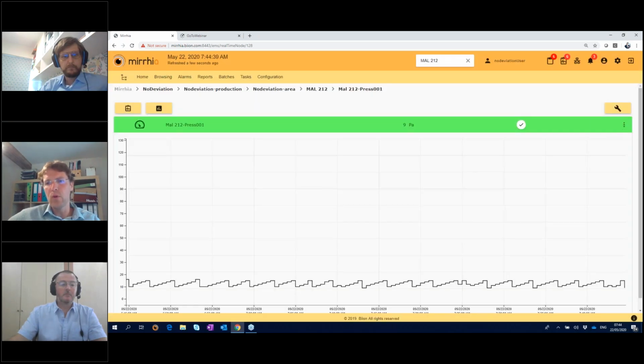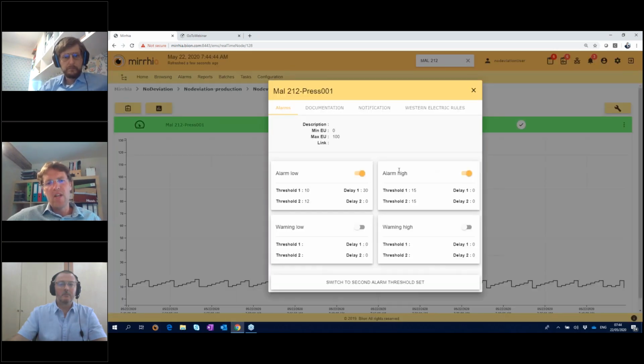Also, if I look at the properties of these sensors, you see that we manage alarm and warning, and we manage 2 sets of thresholds. Of course we manage delay too. This can be useful for pressure sensors, to make sure we don't get an alarm every time we open a door. And as I said, we manage 2 sets of thresholds.